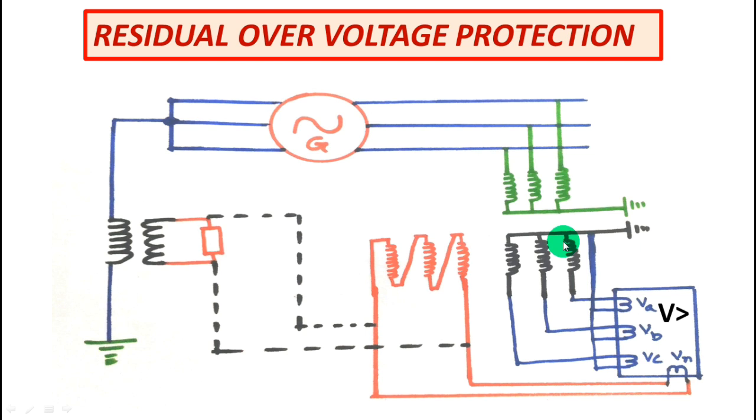So for implementing this scheme, this first scheme where the voltage neutral voltage will be or residual voltage will be calculated by the relay, you have to either select 3 single phase PT or a 5 limb 3 phase PT.